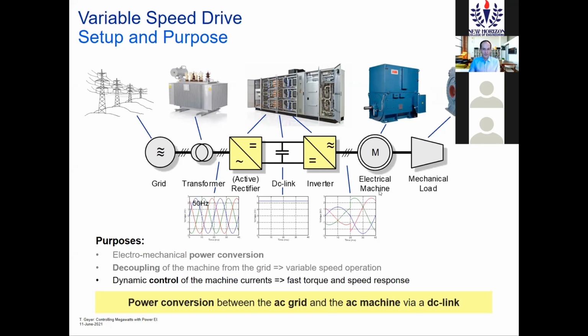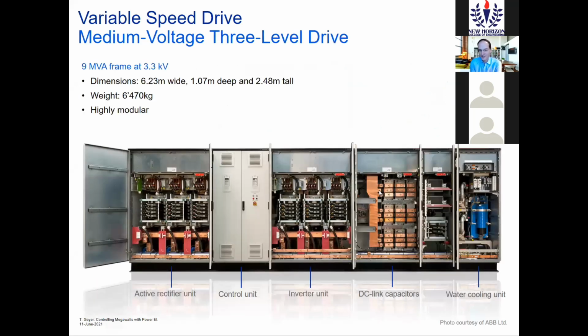So these are variable speed drives, and an example would be a medium voltage variable speed drive. Medium voltage means we're talking about voltages above 1 kilovolt, 1000 volt, and below 35,000 volt. And this would be a 9 megavolt ampere frame with an output voltage of 3.3 kilovolt, around 6 meters long, 2.5 meters tall, a meter deep, and weighs 6.5 metric tons. And it's highly modular. It's a bit like Lego.